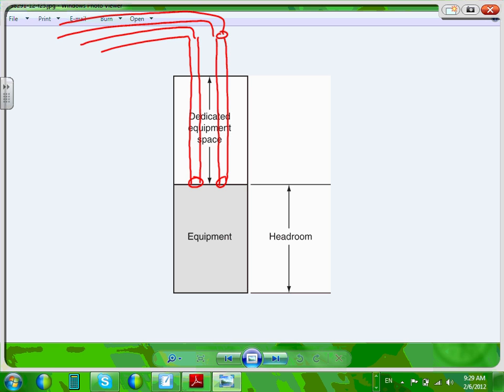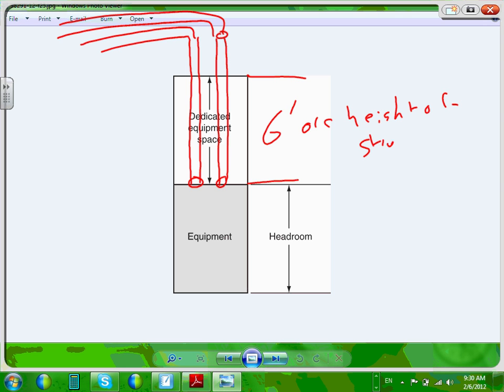In order for you to bring your conduits and not find a big 2 by 2 feet duct for the air handling unit right above your switchgear, so what are we going to do? By law, well, it is the law, nobody can enter this 10 feet. And by the way, this goes all the way 6 feet or the height of the structural ceiling. So if my equipment is right here, and the structural ceiling is 6 feet above my head, or the structural ceiling height, if it's below 6 feet, you're not going to bust through the structural ceiling. But you can have a suspended ceiling right here in front of it. If I'm a switchgear, I can pull right through the suspended ceiling and take my conduits up.